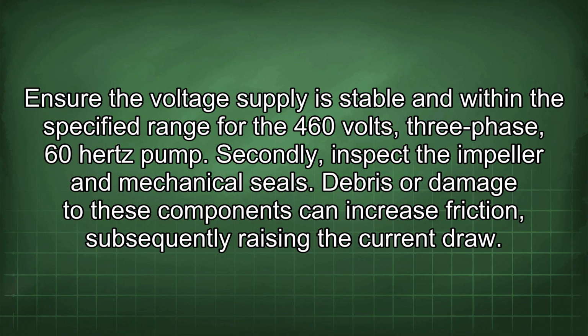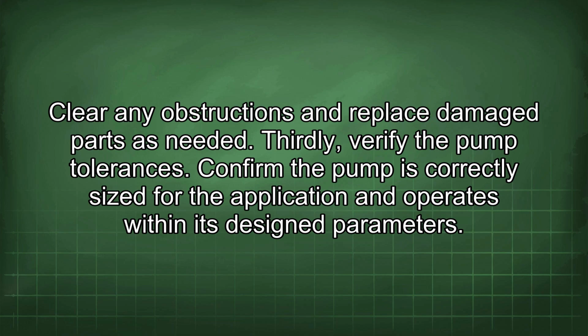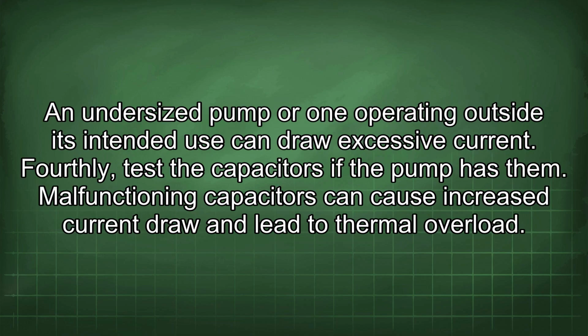Secondly, inspect the impeller and mechanical seals. Debris or damage to these components can increase friction, subsequently raising the current draw. Clear any obstructions and replace damaged parts as needed. Thirdly, verify the pump tolerances. Confirm the pump is correctly sized for the application and operates within its design parameters. An undersized pump or one operating outside its intended use can draw excessive current.